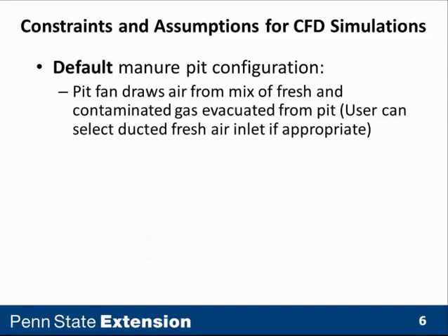The default manure configuration assumes that the pit fan, the manure pit ventilation fan, draws air from a mix of fresh and contaminated gas evacuated from the pit. Now, the user can override that.